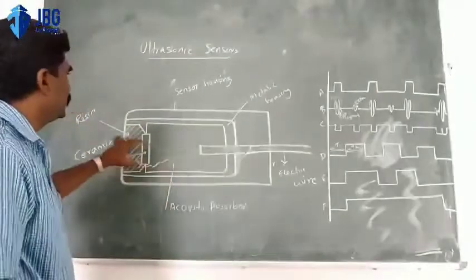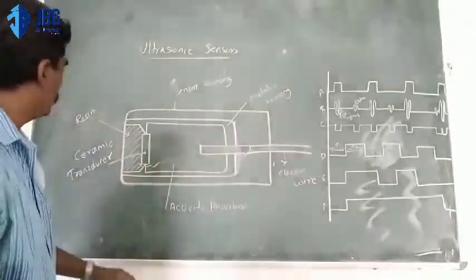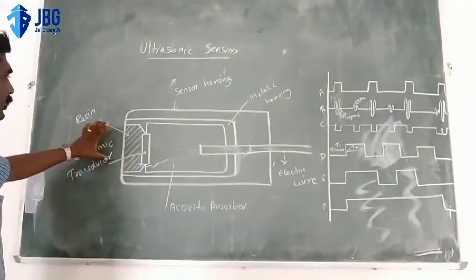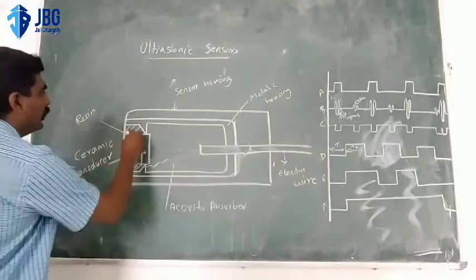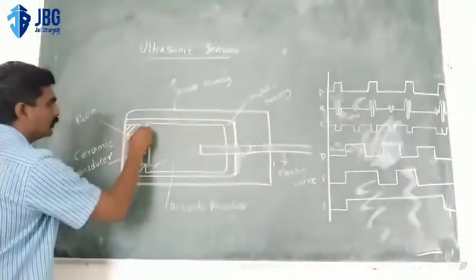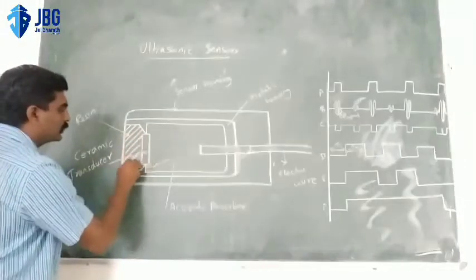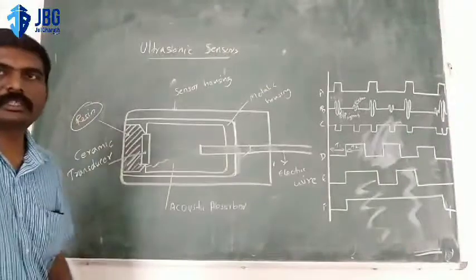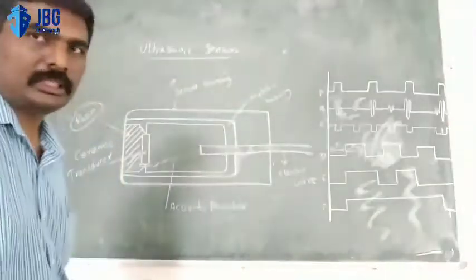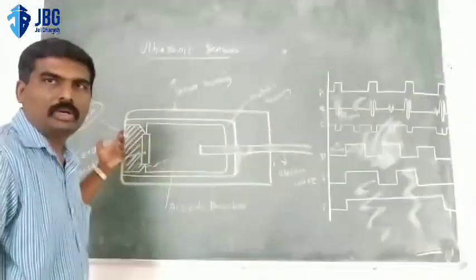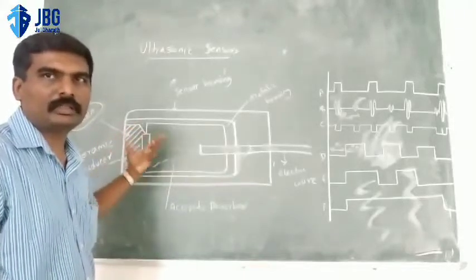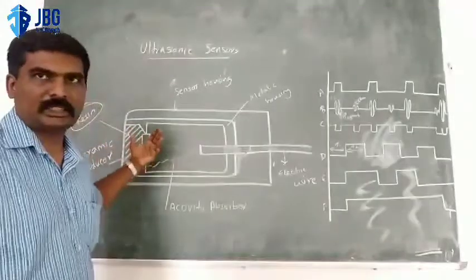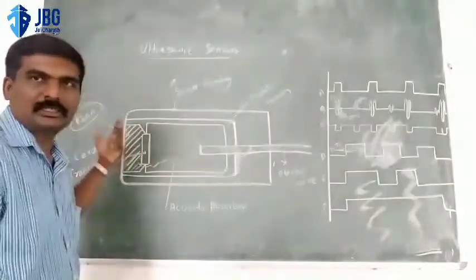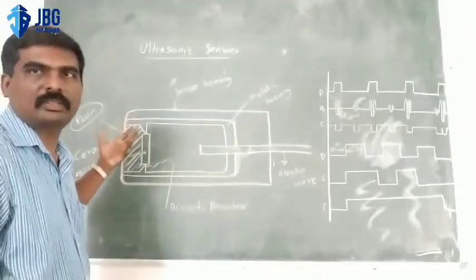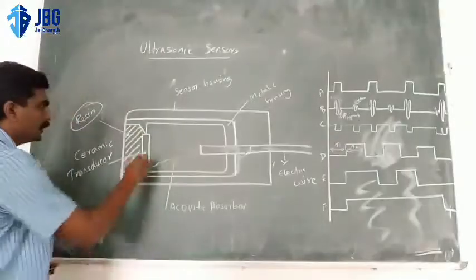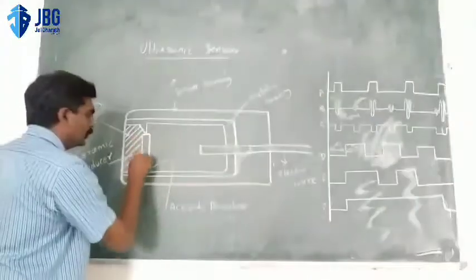Let's see what's in the ultrasonic transducer. Here is a resin area. This marked region is filled with resin that will protect from moisture, atmospheric factors, dust, etc. Here is the ceramic transducer.